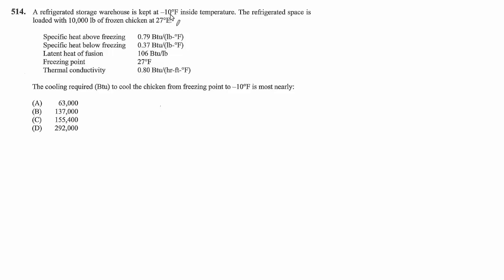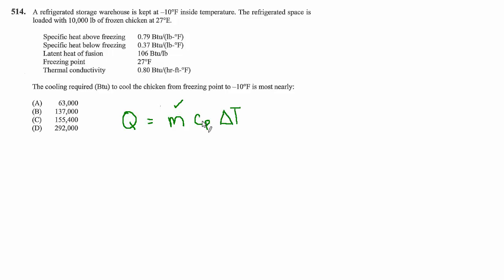So this can be done entirely as a Q equals MCP delta T problem and we know the mass is 10,000 pounds and we know the specific heat capacity because that's been given to us. It's below freezing so we're going to use this one and we know the delta T it has to go from 27 down to negative 10 so this is a pretty straightforward substitution.